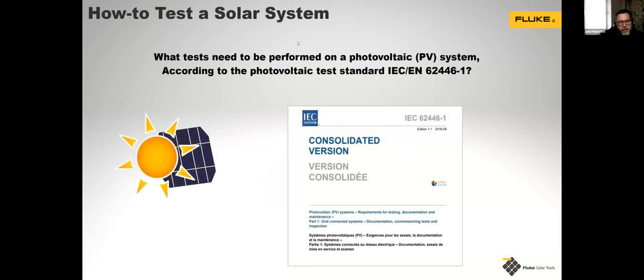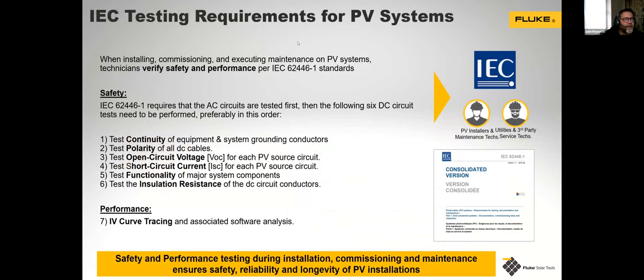All of the photovoltaic systems, PV systems, can be tested against the test standard IEC 62446-1. This comes in several languages, but everything that we talk about today will be in accordance with this 62446-1. Okay, so IEC testing requirements basically says that when installing, commissioning, and executing maintenance on PV systems, technicians verify safety and performance as per the standards.